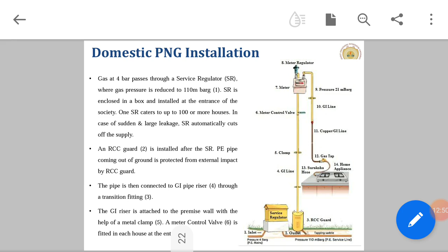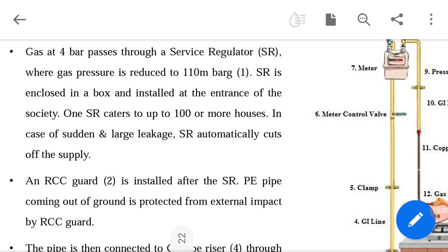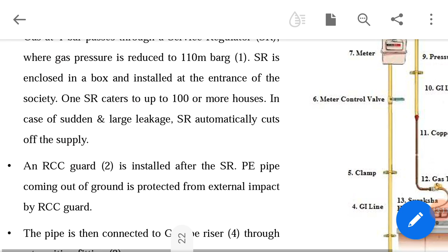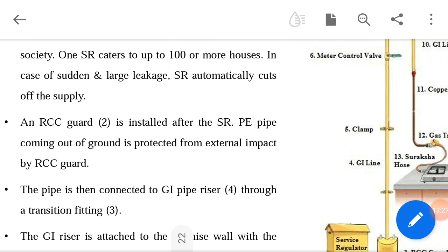Now, how does the domestic PNG installation happen? I'll show you a diagram shortly. Gas at 4 bar passes through a service regulator where gas pressure is reduced to 110 millibar. The SR is enclosed in a box and installed at the entrance of the society. One SR caters to up to 100 or more houses. In case of sudden large leakage, the SR automatically cuts off the supply. An RCC guard is installed after the SR. The PE pipe coming out of the ground is protected from external impact by the RCC guard. The pipe is then connected to the GI pipe riser through a transition fitting.